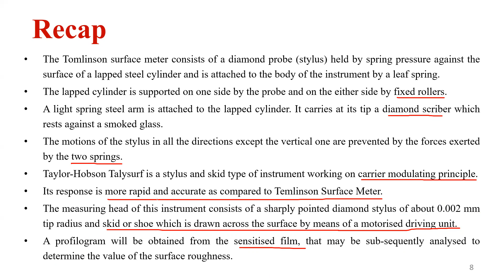The Taylor-Hobson Talysurf is a stylus and skid type of instrument working on a carrier modulating principle. Its response is more rapid and accurate as compared to the Tomlinson surface meter. The measuring head of this instrument consists of a sharply pointed diamond stylus of about 0.002 mm tip radius, and a skid or shoe which is drawn across the surface by means of a motorized driving unit. And then we understood how the profilogram works. It is obtained from the sensitized film, which may subsequently be analyzed to determine the value of the surface roughness.